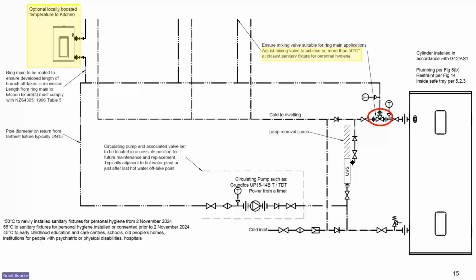as to whether you want to put a little under sink cylinder in the kitchen or the scullery to boost that temperature from 50 degrees up to perhaps 60 degrees at the kitchen sinks, because 50 degrees might be a bit shy, particularly if it's a long run and you're losing 1 or 2 degrees. You might be down to 49, 48 degrees. So have a chat with your customer if it's a new fixtures, new building, about whether they want to invest in a small electric water heater, 30 litres or something, to boost that temperature up at the kitchen sink if they think the 50 degrees less a bit's not going to rinse the gravy off the plates when they're washing up.